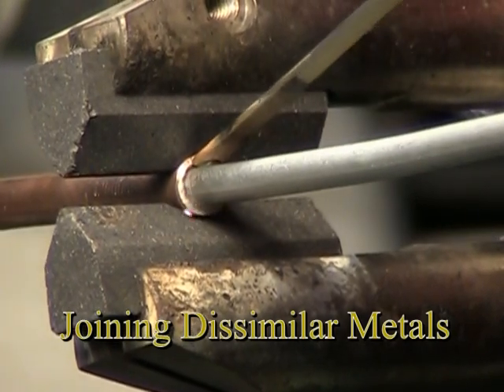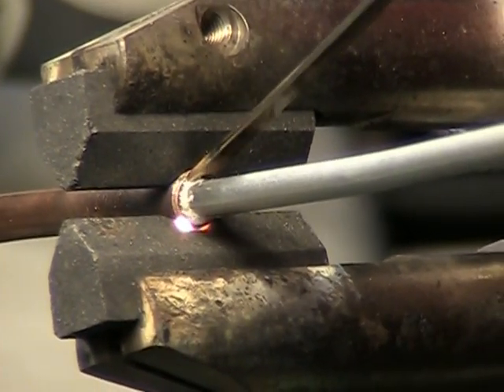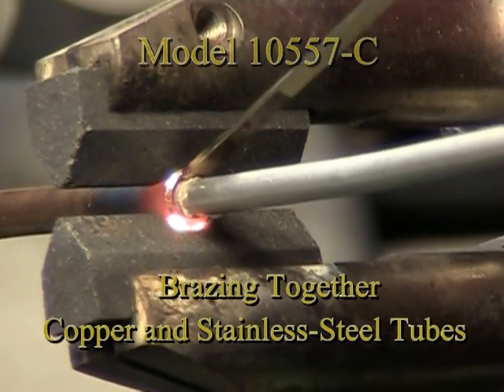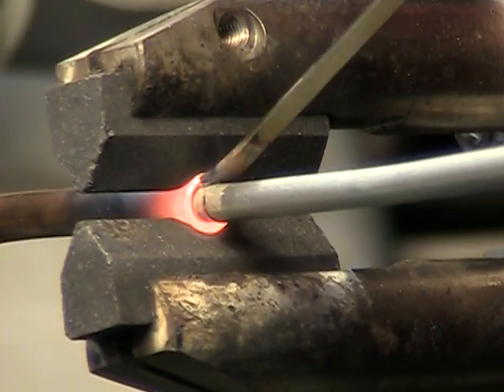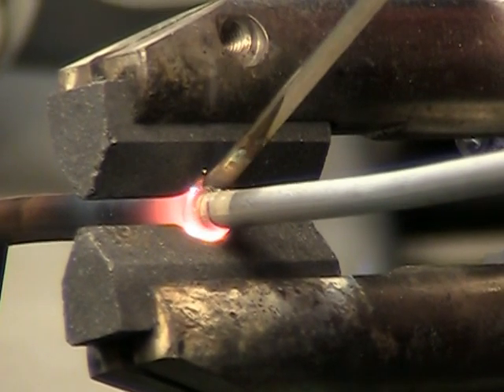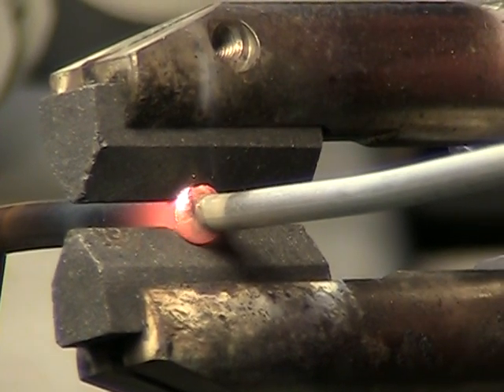A question that is often asked by refrigeration service and repair technicians is whether or not it is possible to braze copper and stainless steel tubing together using American Beauty resistance brazing equipment. As demonstrated in this segment of our video, using the model 10557-C handpiece, we are able to resistance braze these dissimilar metal tubes together.